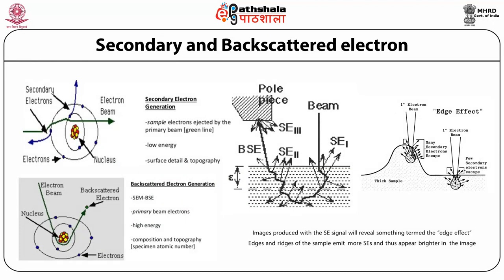Secondary electrons are produced from the emission of valence electrons of constituent atoms in the specimen when the incident beam enters. Since the energy of secondary electrons is very small, those generated in deep regions are quickly absorbed by the specimen. Only those generated at the top surface are emitted outside. This means secondary electrons are very sensitive to the surface, and the difference in brightness of the crystal surface is due to the difference in the incident angle of the electron beam. Thus, secondary electrons are used to observe the topography of the specimen surface.